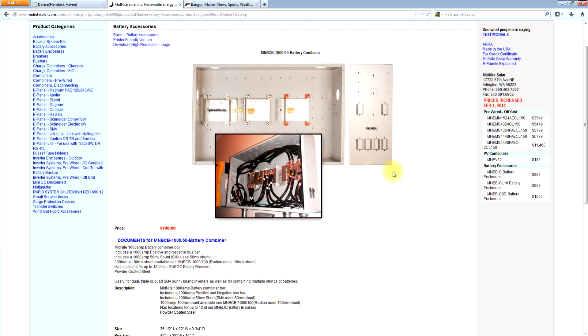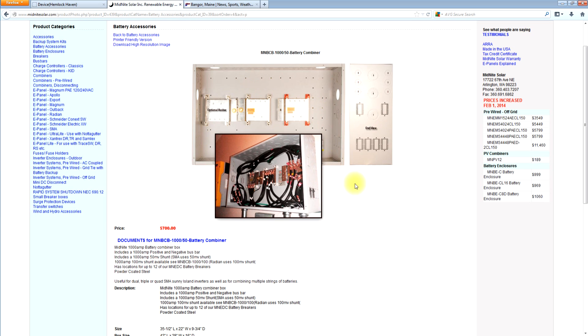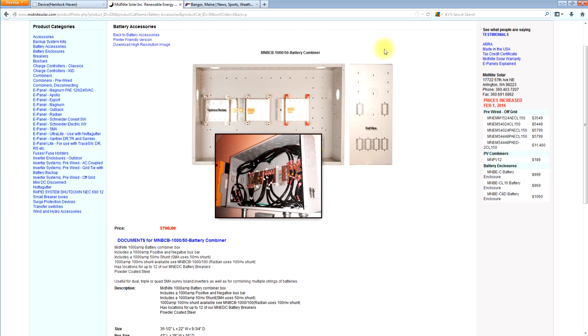Like I say, just kind of a nice universal box. Really elegant for doing three or four sunny islands. It also works really well for doing multi cluster systems of sunny islands. And those of you that are familiar, for multi cluster will know it could be four groups of four sunny islands, or four groups of three sunny islands stacked in three phase. So it could be like twelve sunny islands on a single system. And in that case, you could do a battery combiner box for each cluster and put the three 250 amp breakers in each box for each cluster. And then you get the four clusters beside each other and then you have the multi cluster box for the AC side of things.